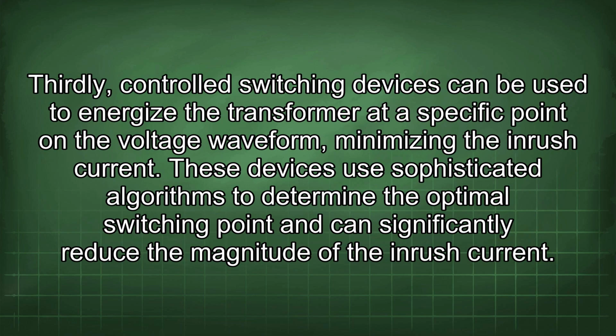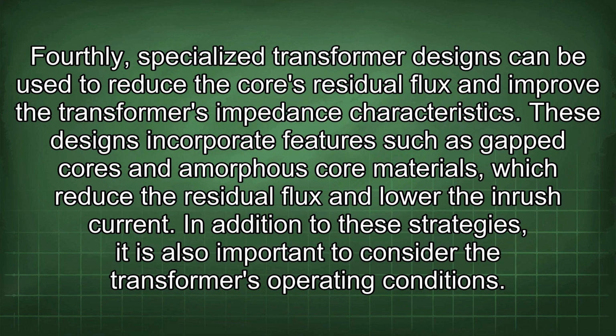Thirdly, controlled switching devices can be used to energize the transformer at a specific point on the voltage waveform, minimizing the inrush current. These devices use sophisticated algorithms to determine the optimal switching point and can significantly reduce the magnitude of the inrush current. Fourthly, specialized transformer designs can be used to reduce the core's residual flux and improve the transformer's impedance characteristics. These designs incorporate features such as gapped cores and amorphous core materials, which reduce the residual flux and lower the inrush current.